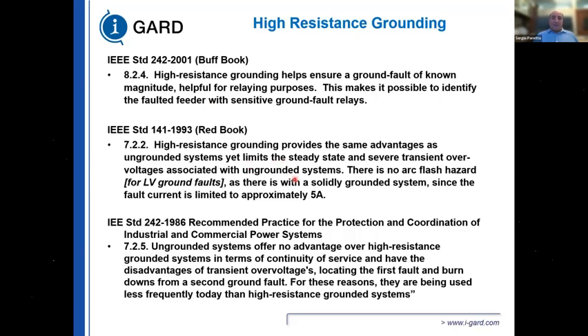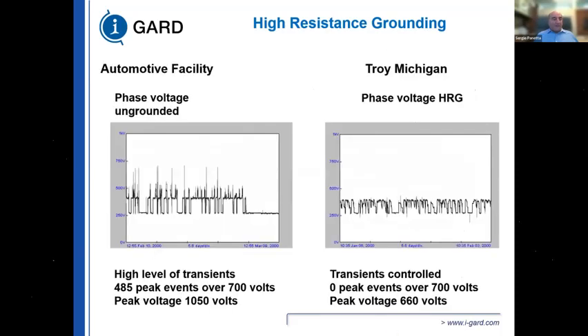High resistance ground provides the same advantage as an ungrounded system, but limits the fault current to a low value, 5 amps, providing you a means of locating where the fault is and clearing the fault in a timely manner. So that same facility that we saw in Michigan, where we experienced 485 peak events over 700 volts, after converting to a resistance grounded system, had 0 peak events over 700 volts.